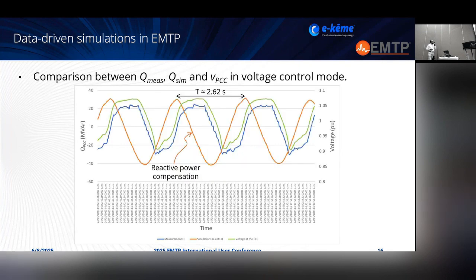Here is a magnified view of this comparison between the measured value and the simulated results. We can see in green the voltage at the point of interconnection, and in blue the measurement of the reactive power. We can see that both measurements are in phase. And once we simulated the reactive power of the wind farm under the same conditions, we can see a reactive power compensation on either the capacitive side or the inductive side. It's important to note that these are low frequency oscillations with a period of around 2.62 seconds, or approximately 0.38 to 0.4 hertz.